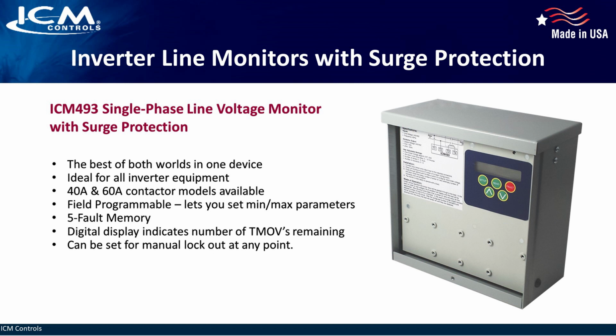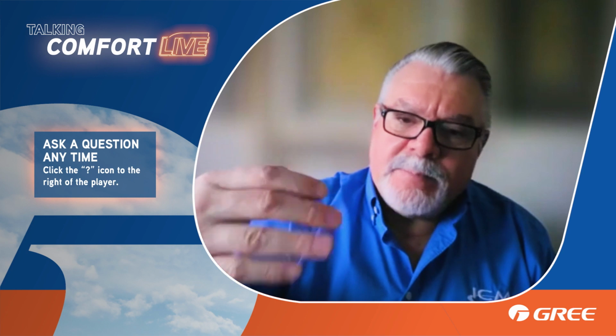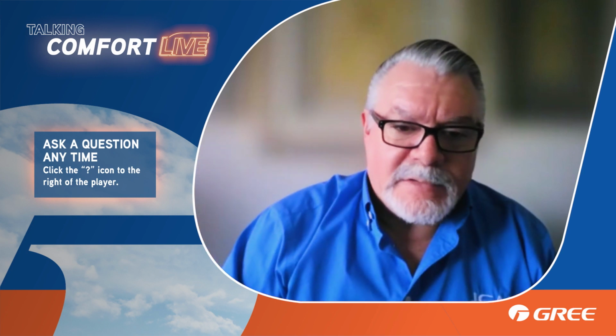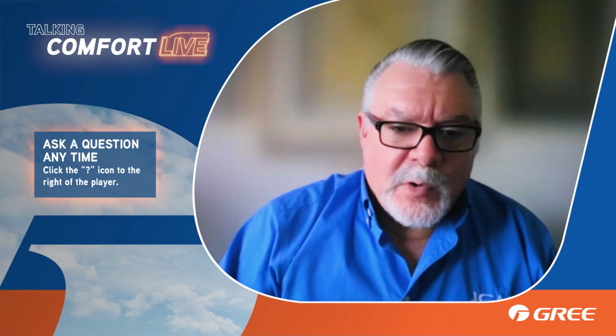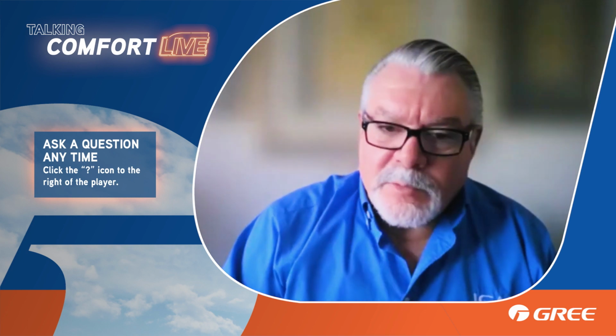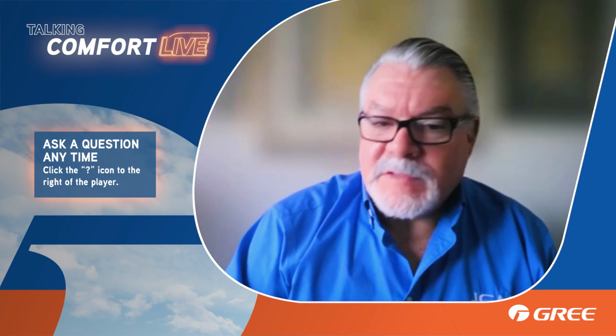And we've got those in both the 40 amp and 60 amp contactor models. And they're fully field programmable. Lets you set min and max parameters for over and under voltage. It has a 5-fault memory, so it'll tell you the exact voltage at the time of fault. And then the display also indicates the number of TMOVs you have remaining. So it has 5 on board. And as TMOVs get used up, it'll say you have 4 remaining, you have 3 remaining, and so on. These things are fully programmable. They can be set for auto retry or manual lockout if you desire.